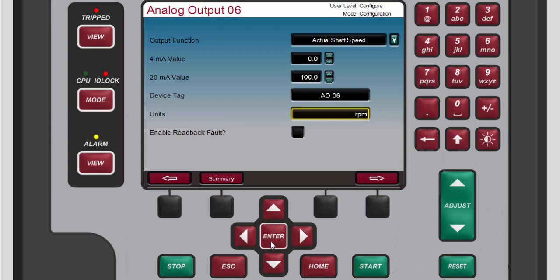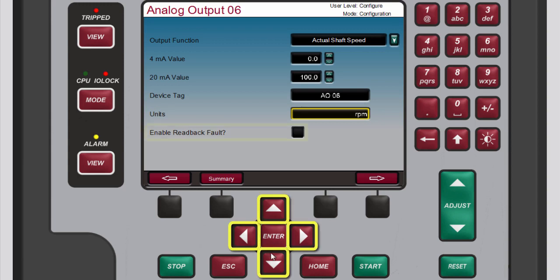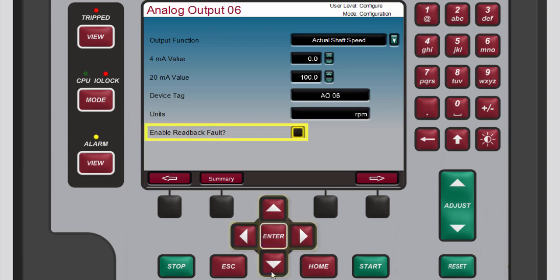Use the navigation cross keys to highlight the enable readback fault box. Enable this function to issue an alarm when the analog channel has a fault. A fault will be determined if the current drops below the failure level, or if the difference between the current detected on the source and return wires of the circuit is greater than 5%.